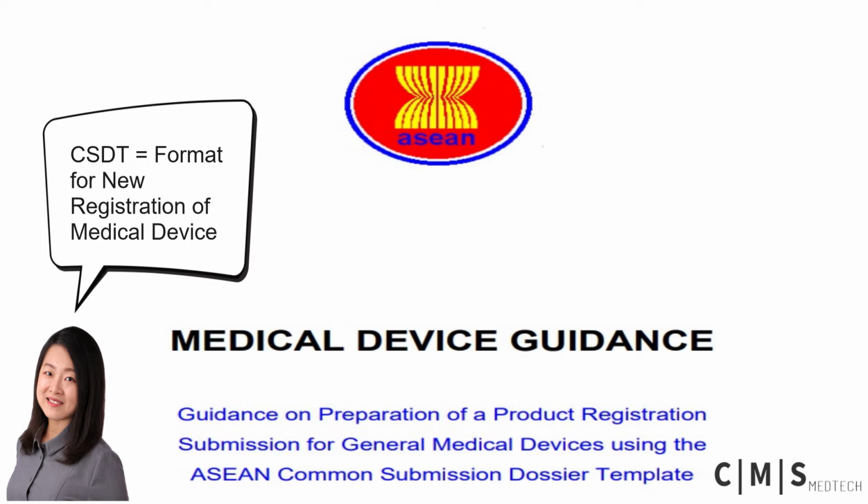respective ASEAN countries. If you do happen to see the CSDT before, then you might have spotted a high level of similarities between the EU technical file and the CSDT. But I would like to highlight the main difference between the two. The technical file needs to be maintained and updated throughout the entire lifetime of the medical device. The technical file is subjected to audit on an annual basis by the notified body to ensure the medical device continues to remain under CE certification, which in turn enables the medical device to be supplied in EU regions continuously.